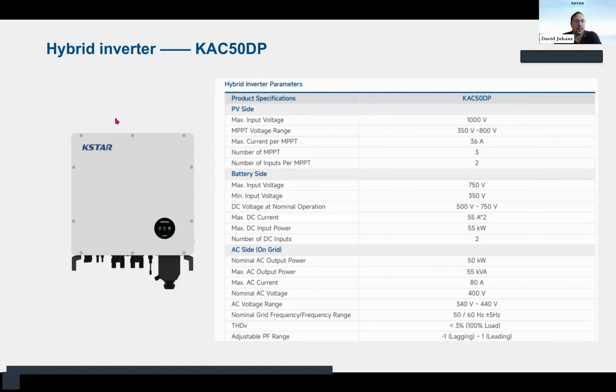These are some parameters regarding the inverters on the right side of the cabinet. It has a nominal power of 50 kilowatts, and the maximum input voltage regarding the photovoltaic is 1000 volts. The maximum current per MPPT is 36 amps, and regarding the calculation, the short circuit current per MPPT is more than that. It's 40. The maximum input voltage of the battery pack clusters is 750 volts, and the DC current inside is 2 times 55 amps.